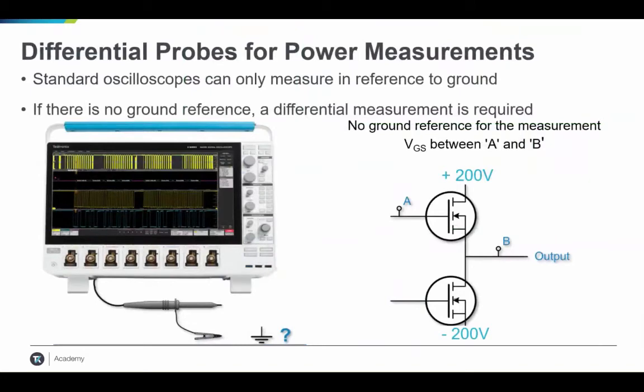Using a differential probe for power measurements is important. Standard oscilloscopes can only measure in reference to ground, so if there's no ground reference, a differential measurement is required. In a simple half-bridge transistor configuration, the potential at the high-voltage DC bus is plus 200 volts versus minus 200 volts at the bottom. If you want to make a measurement between points A and B, you can't use a single-ended probe because the output at point B has some voltage potential and you can't use the ground to connect to that. Using a differential probe in this case is ideal and what we recommend.